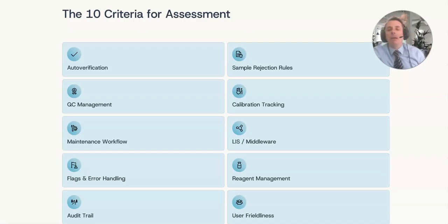The main criteria used for the ranking of the biochemical analyzers are the ones you see on your screen. For the first one, can the analyzer or its connected system release results automatically using rules? Yep, most of them do. Sample rejection. Can it detect problematic samples and reject or flag them appropriately? QC management. Does it support proper quality control rules, charts, and lockout behavior?